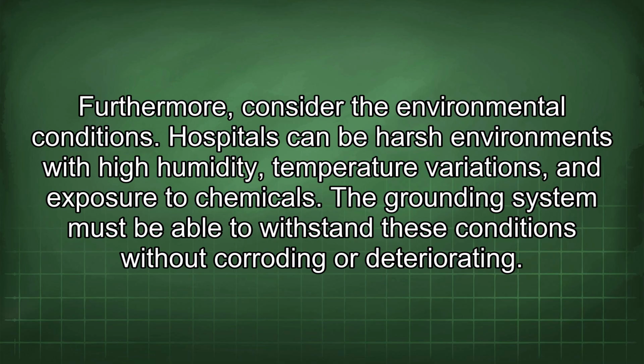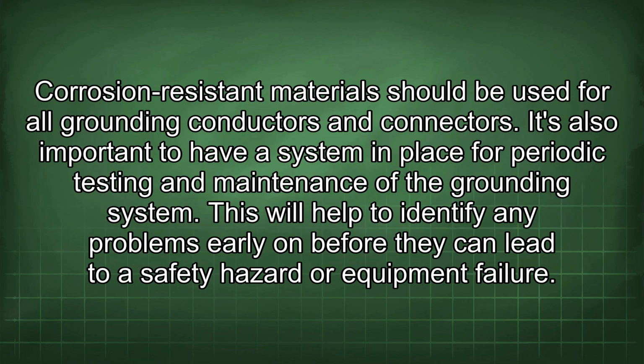Furthermore, consider the environmental conditions. Hospitals can be harsh environments with high humidity, temperature variations, and exposure to chemicals. The grounding system must be able to withstand these conditions without corroding or deteriorating. Corrosion-resistant materials should be used for all grounding conductors and connectors.